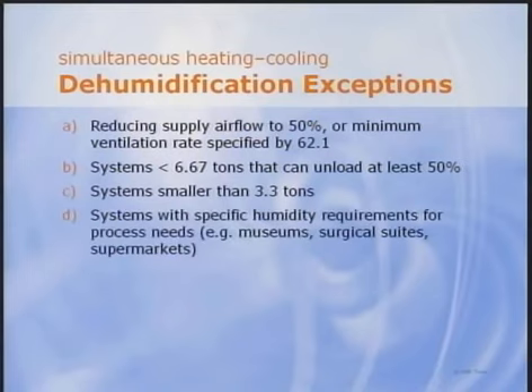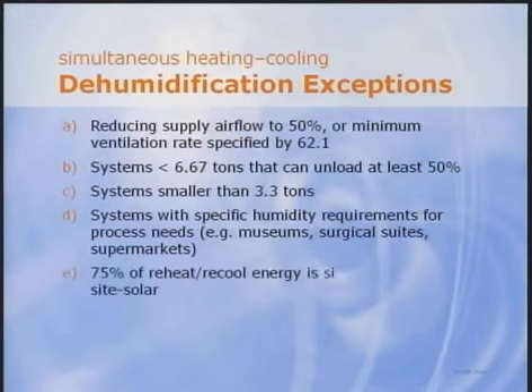Also accepted are humidity-sensitive applications, including computer rooms, museums, surgical suites, supermarkets, and ice arenas. So these and similar applications can use reheat for humidity control. Using exception E, reheat may be used at any time if 75% of that reheat energy is site recovered or site solar. We've seen many projects use this exception and recover heat, either directly from the refrigerant or from condenser water. For example, on a water-cooled chiller with a heat recovery condenser, it can help satisfy this exception.